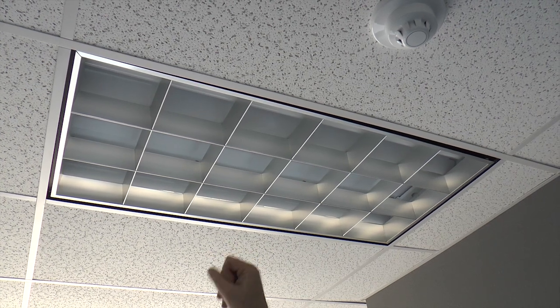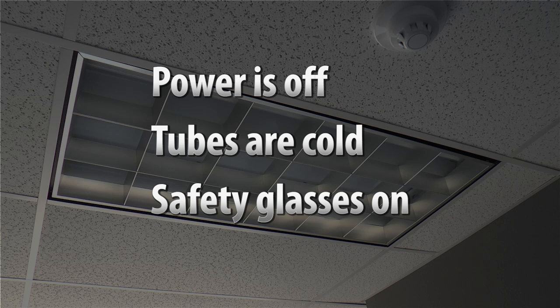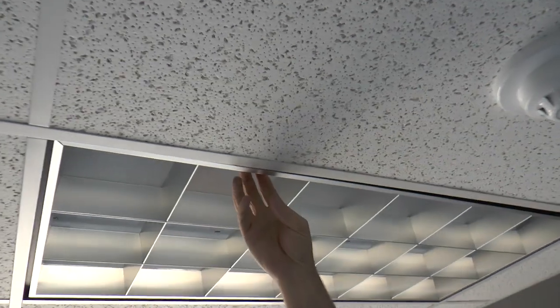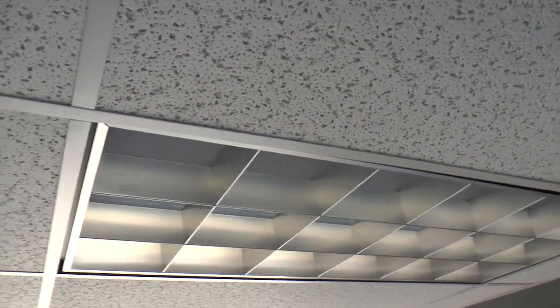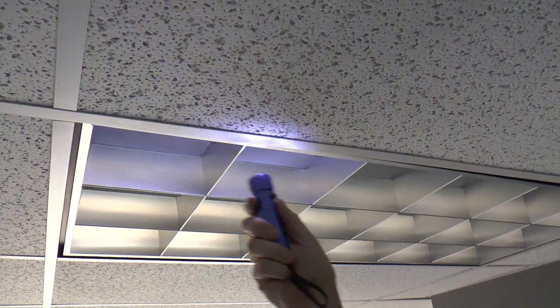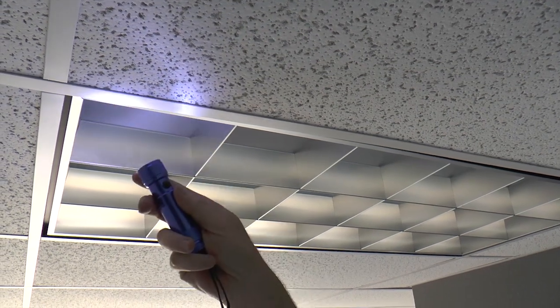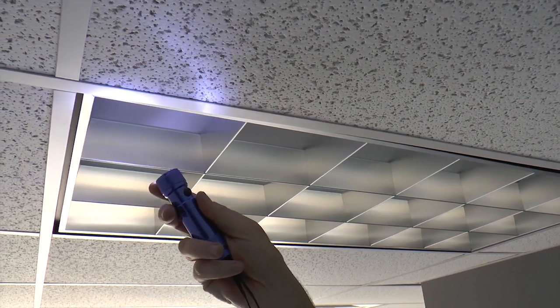And put in our LEDs. So the first step is to move these louvers out of the way. And I always make sure that the power is off, the tubes are cold, I have my protective eyewear on. Now all the light fixtures open up slightly differently. Usually these grates swing out of the way. And I bring a flashlight so I can look up inside here and find the springs that are holding this trim in place. So I see the spring up there.